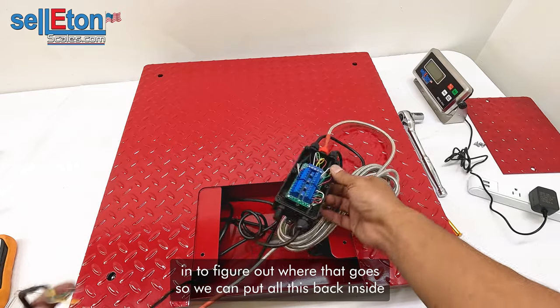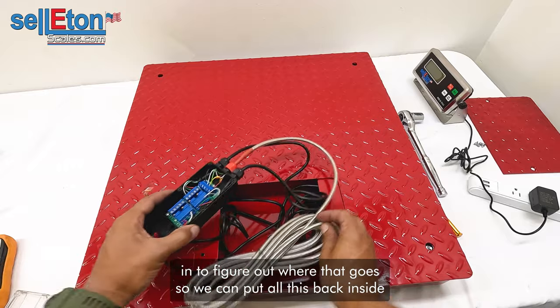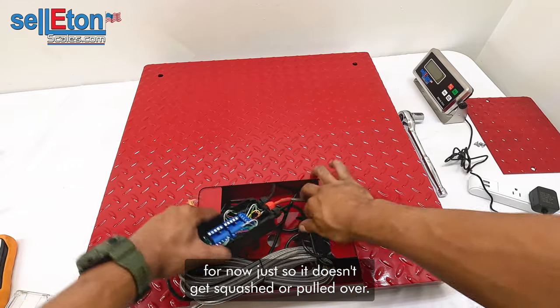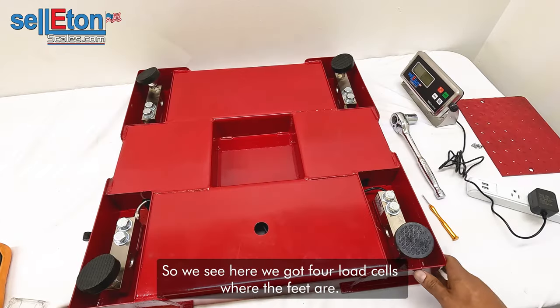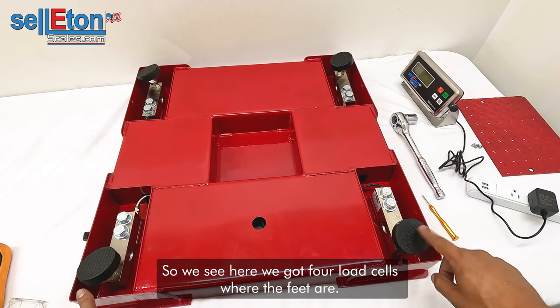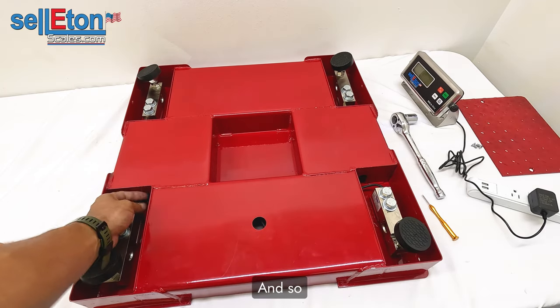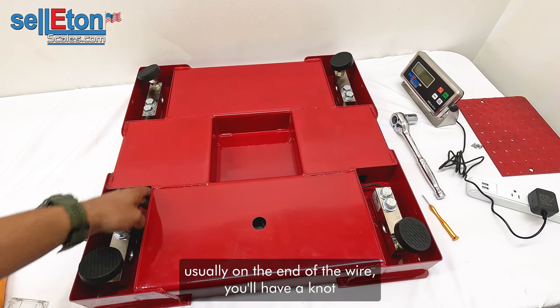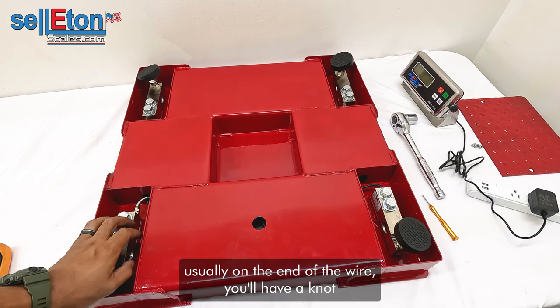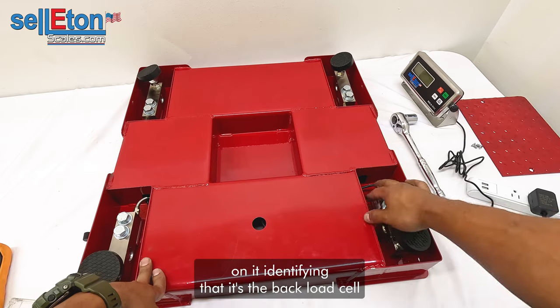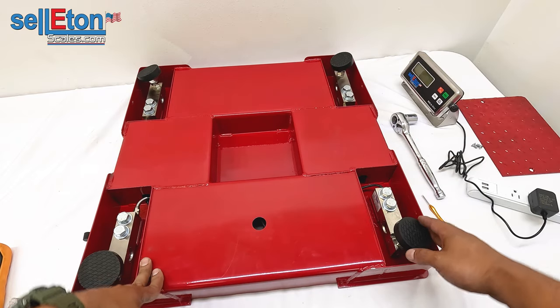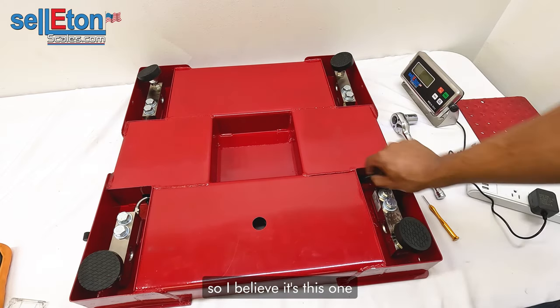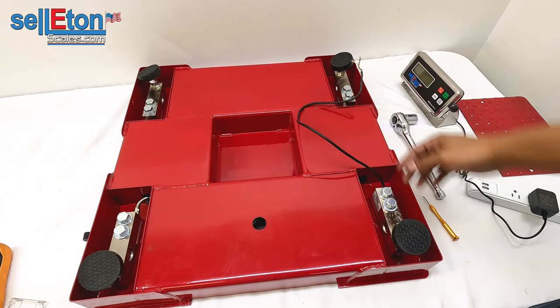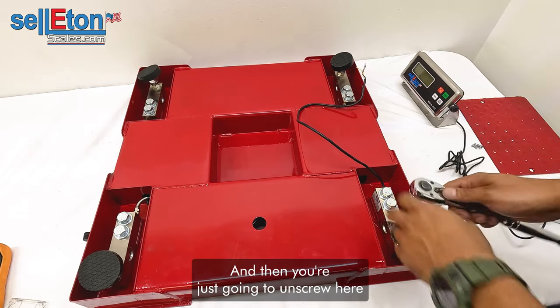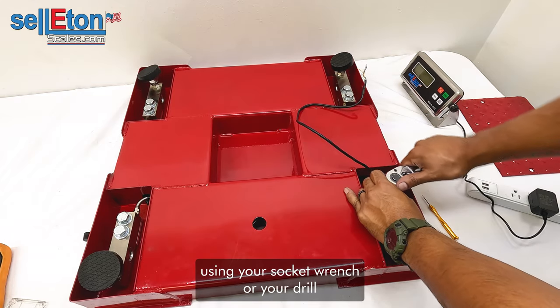I'm gonna figure out where that goes. So we can put all this back inside for now, just so it doesn't get squashed when we flip it over. So we see here, we got four load cells where the feet are, 1, 2, 3, 4. And usually on the end of the wire, you'll have a knot on it identifying that it's the back load cell. So I believe it's this one, which it is. And then you're just gonna unscrew it here using your socket wrench or your drill.